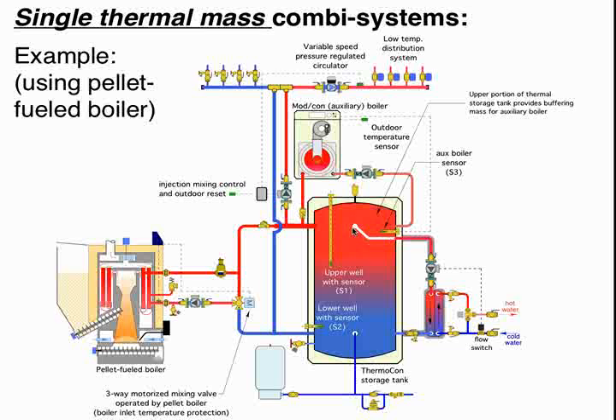We've actually got 3 connections up on the high sidewall. So rather than tee in here, we can just run a separate pipe in. We take hot water from the top of the tank, go down through the primary side of the heat exchanger, go back into the tank, and simultaneously our cold domestic water makes a pass through the secondary side of the heat exchanger, comes out. We'll put in an anti-scald rated tempering valve and then off to our load. So what we're doing with this is we're actually using the thermal mass of the thermocon tank for buffering both the space heating load as well as providing domestic hot water.